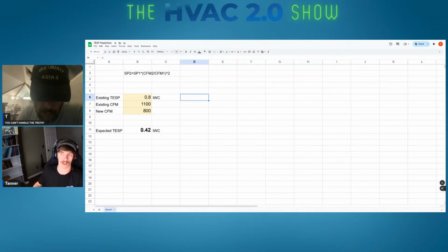That bump comes from the scenario where it's a 4-ton system, but the PSC motor is only moving 1,000 or 1,100 CFM, and then you put in a new EC motor that's going to move 1,400 CFM, so you get that static pressure bump because you're trying to create a gallon and a half of flow in a 1-gallon jug.